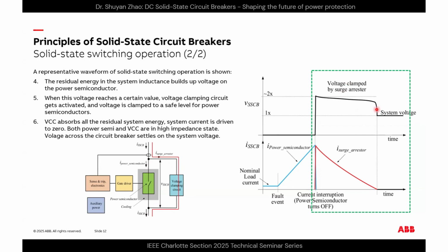Then that comes to this part. The residual energy, because the system typically has inductance or impedance. Before the fault interruption, there is some current flowing through that line inductance, or impedance, which stores some energy in the system. And when we turn off the semiconductor, this residual energy in the system inductance builds up the voltage on the power semiconductor device here. So it will rise very quickly.